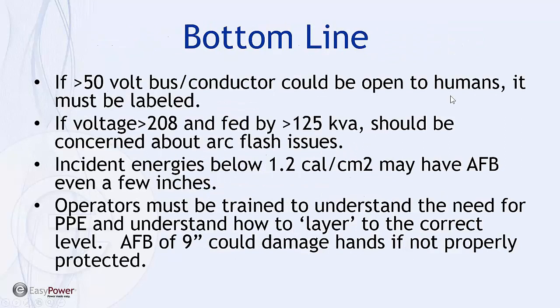So when we get to the bottom line: if there is more than 50 volt bus or conductor exposed that humans can come near, they need a label. If during normal operation the equipment needs to be maintained, inspected, or opened up so bare conductors are exposed to humans, it needs a label. If the voltage is greater than 208 and it's fed by a transformer greater than 125 kVA, there should be a concern about arc flash.